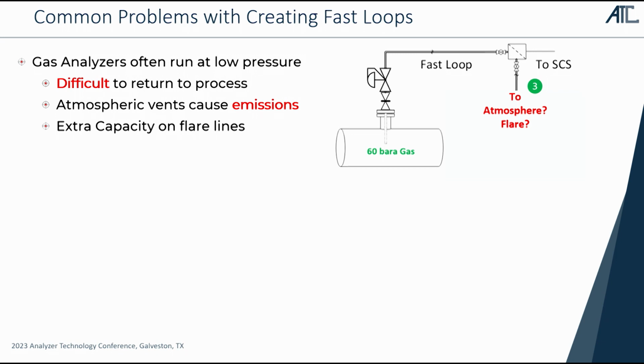If I vent it to atmosphere, which a lot of fast loops will sometimes, and I'm running natural gas, well, now I've got significant methane emissions. And of course, these days, methane is anywhere from 25 to 40 times the greenhouse gas equivalent of CO2. If I've got a 5 liter a minute bypass venting to atmosphere, it's a significant amount of GHG emissions. If I'm taking it to my flare line, I've put extra capacity into my flare. If I've got a whole bunch of analyzers in the plant and they're all venting to the flare header, well, now all of a sudden my environmental guy goes, hey, can you guys put less stuff to my flare?